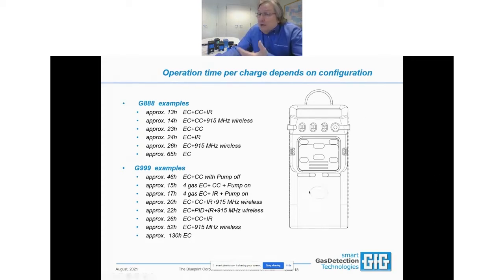In the 999, we have twice as much power, so it makes sense that with a catalytic LEL sensor, with your standard electrochemical, oxygen, and toxic sensors, with the pump turned off, it lasts for 46 hours per charge. If you turn the pump on, it still lasts at least 15 hours. And you know what? I need to modify that slide, because that includes the RF communication turned on as well.